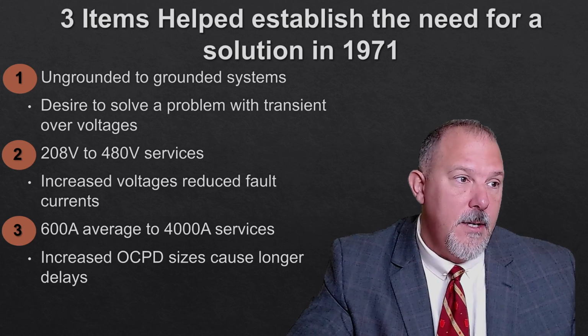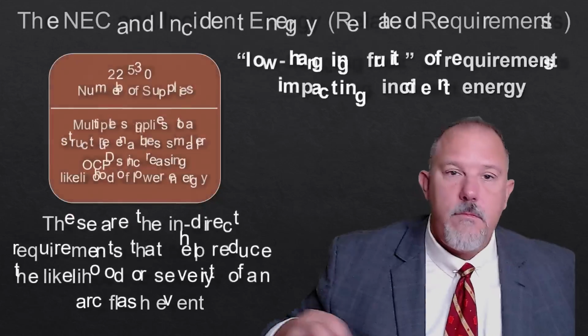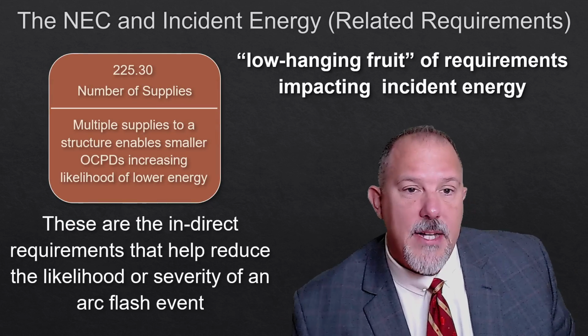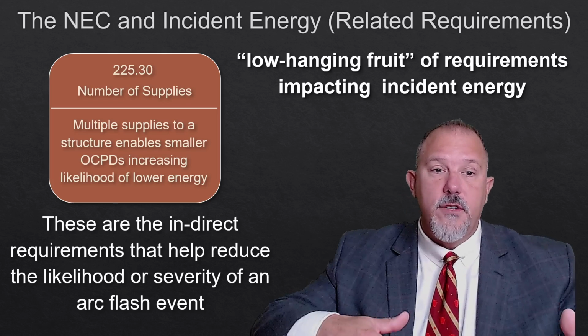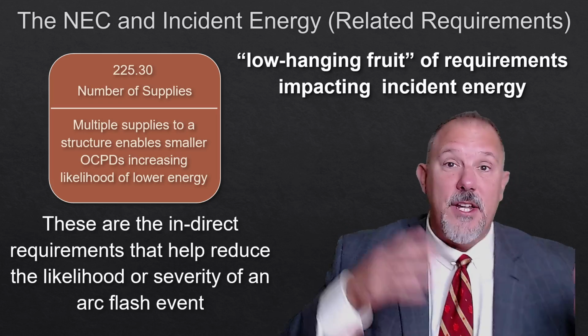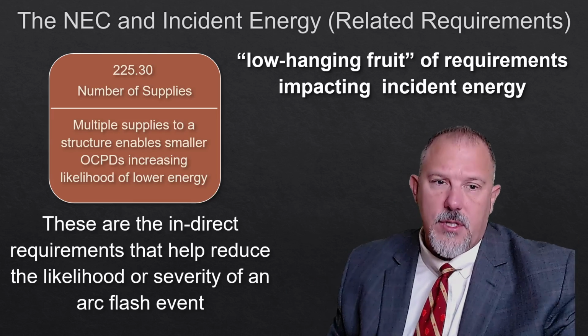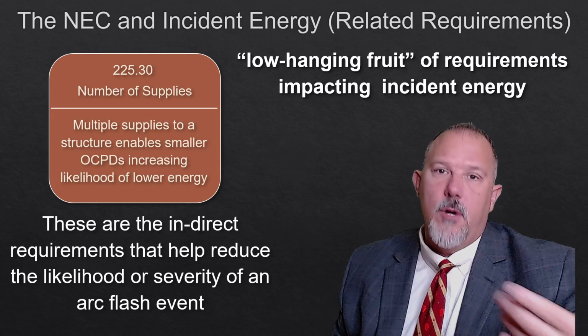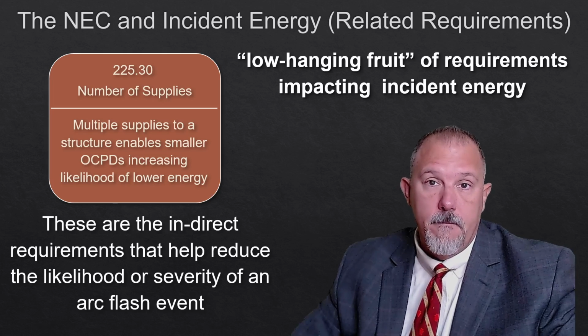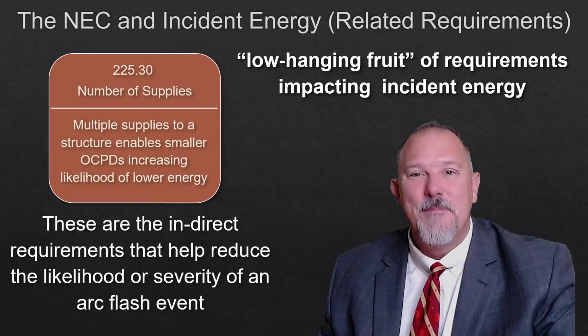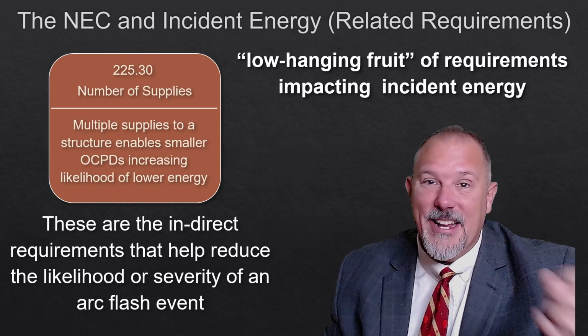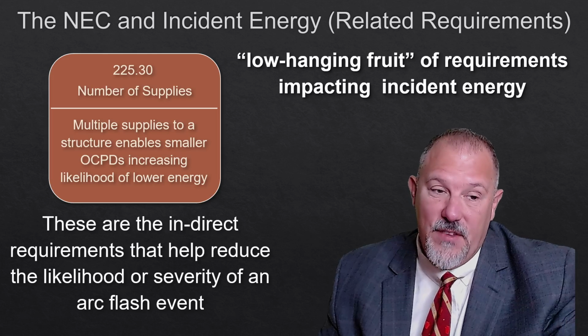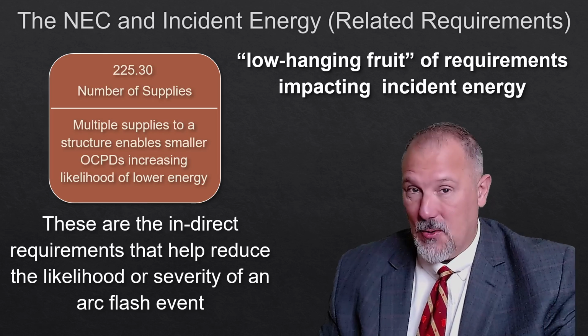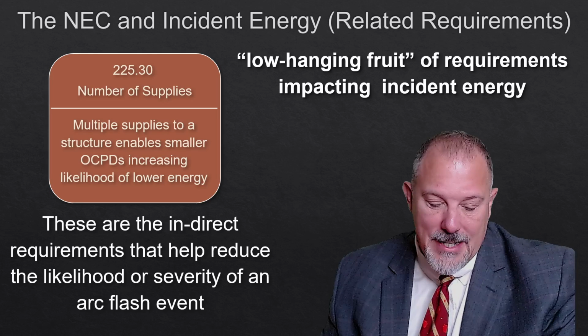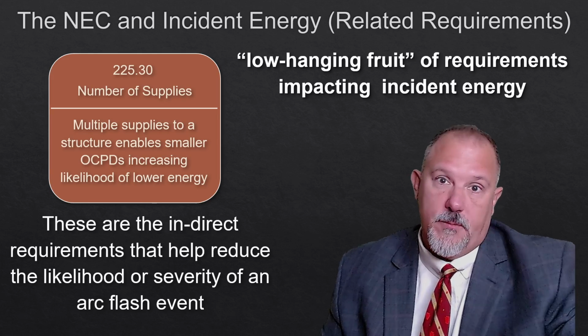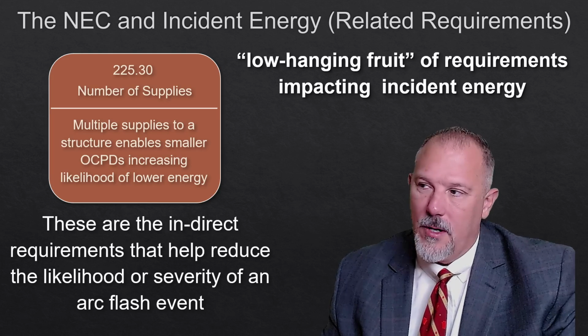Now, another low-hanging fruit is Article 225, number of supplies. Multiple supplies to a structure enables smaller overcurrent devices, increasing the likelihood of lower incident energy. So this was a strategic change, I believe in the 2020 code, that let us put multiple feeders or branch circuits to a structure. And that was to solve the problem of, remember the electric vehicle chargers, where I had to bring 2 feeder circuits to an electric vehicle charger, which violated the National Electrical Code because they said you're only allowed to have 1. I would have to bring 2 because I'm serving 2 vehicles, or possibly more.